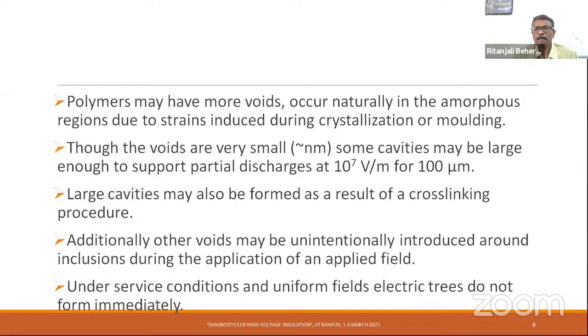Polymers have more voids; they occur naturally in the amorphous regions due to strains induced during the crystallization process. In fact, there were reports that during manufacturing, the gaseous environment makes gas formation or void formation inside very much possible. Though the voids are very small, some cavities may be large enough to support partial discharges at a much higher field of about 10 power 7 volts per meter for 100 microns.